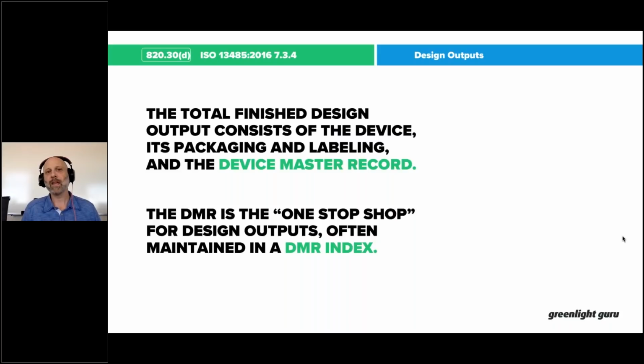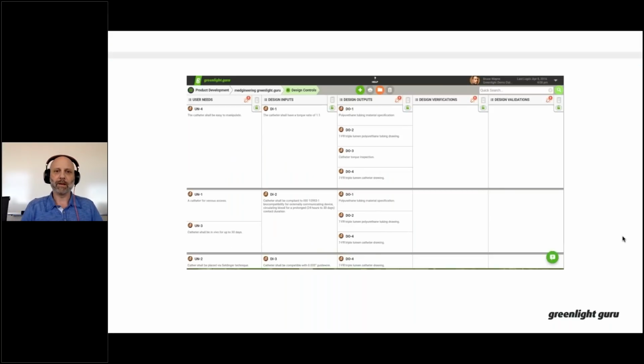use that recipe analogy to describe design outputs, because it is the recipe for your medical device. And the other key thing to think about from a design output standpoint is the design outputs that you're designing and establishing and developing during the product development process. It is the preliminary device master record, because a device master record is more of something that's a production controlled type of thing. But device master record is also the recipe of your product. It just so happens that now this is what we manage and maintain under control once we transfer to manufacturing. But design outputs and device master record, they're the same thing, folks. One's just during development, one is post-development. So keep that in mind.